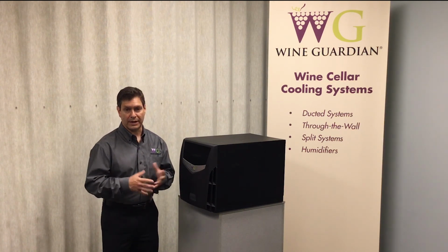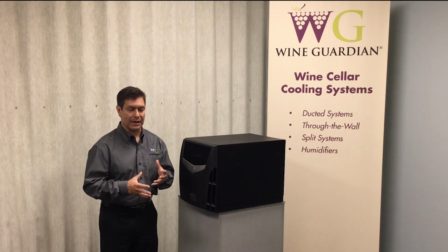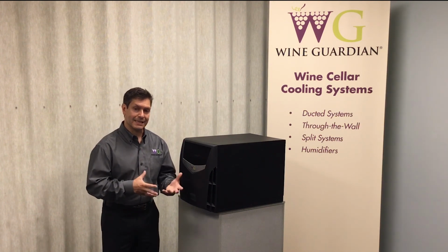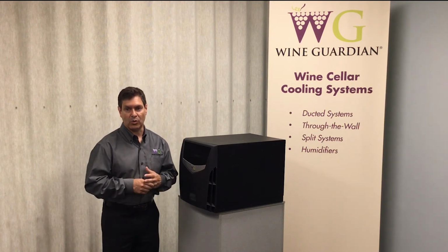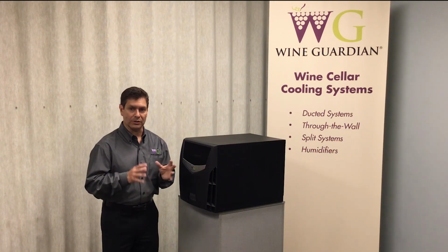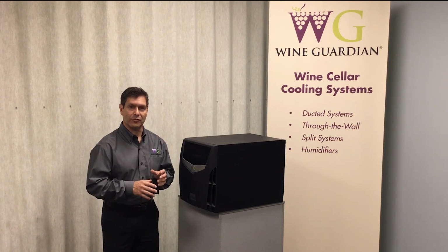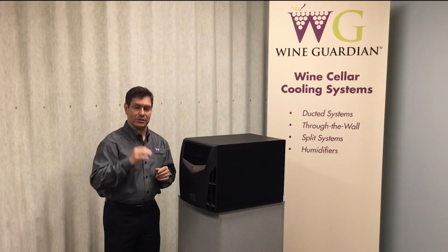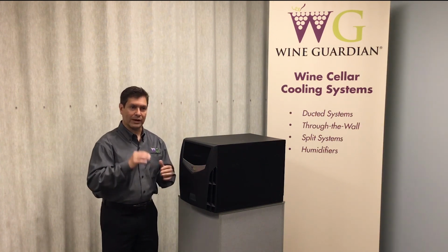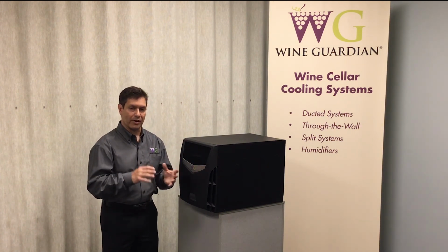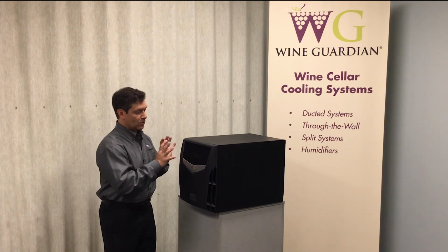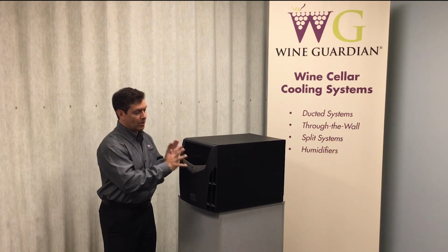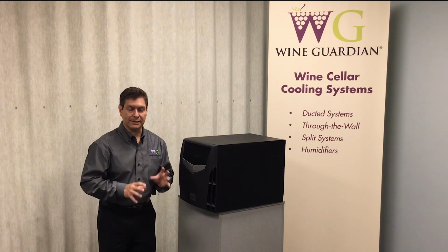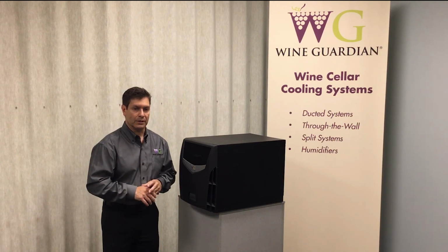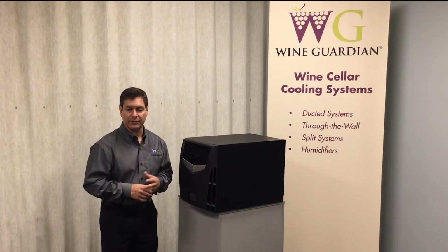So to answer your question, I would strongly suggest against that and try to move it up on the wall to the midpoint or a little bit higher than that. The same holds true for a very high mount of the unit. You don't want it right at the ceiling level. You want to be off the ceiling a bit so that the cold air can really come off the unit and be directed into the center part of the room, so it mixes well and then can return back.